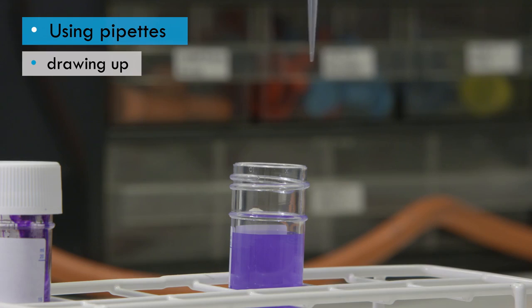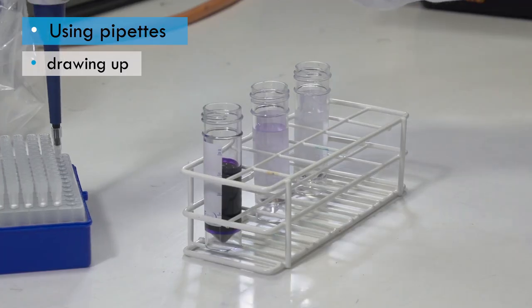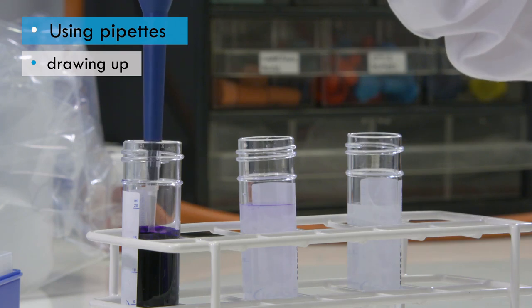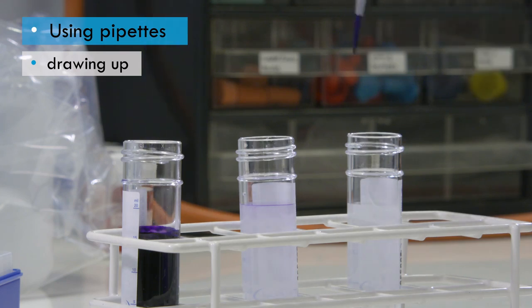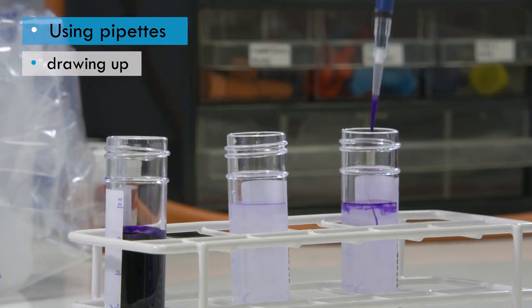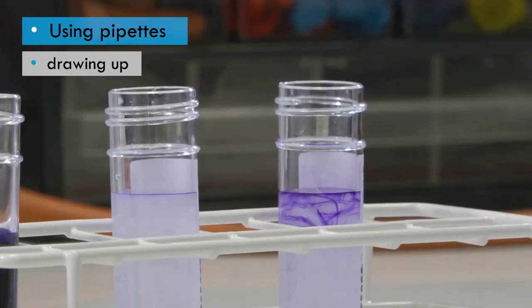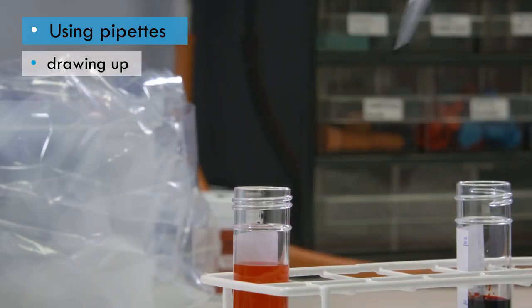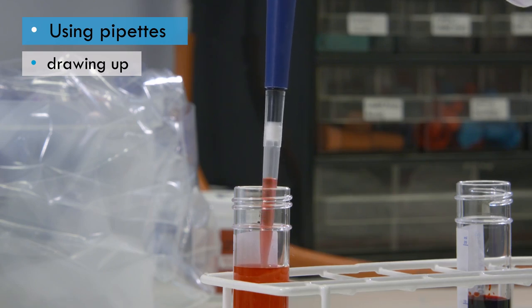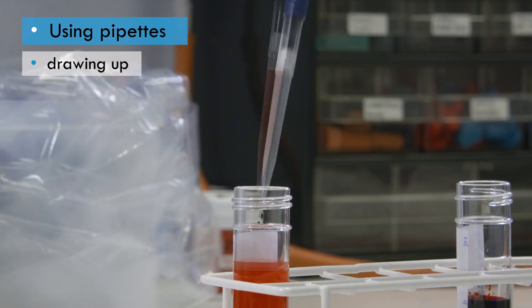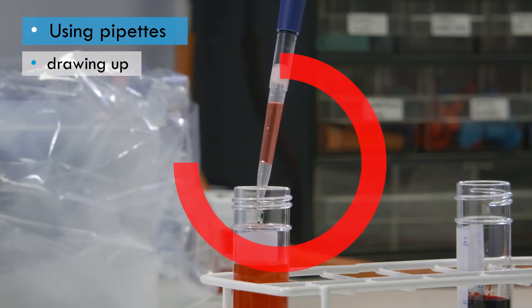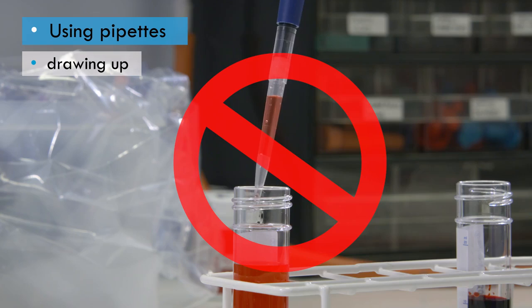When drawing the liquid into the pipette or tip, place the tip just below the surface of the liquid so that you can draw up liquid without drawing up any air. You should avoid getting liquid onto the outside of the pipette tip. As you can see, this adds significant extra material to the transfer, which will reduce accuracy, especially when pipetting small volumes. Draw liquid up slowly to avoid sucking up air. If the action is too quick, then you will trap air and probably contaminate the filter.